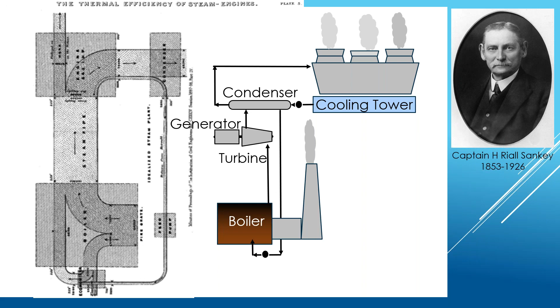Often in rivers, you'll take river water and run it through your condenser, which isn't evaporating the water, but it's adding some temperature to it, having a bit of an environmental impact. Here in the West, though, almost all of our power plants run with cooling towers. We're taking a water source and evaporating it using the latent heat of evaporation in water, 1,000 BTUs a pound. We're able to pretty cost effectively convert water into the energy we need to extract from the condenser. So that's what that process looks like from a component standpoint.